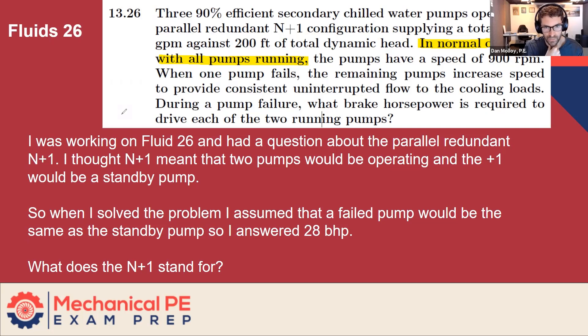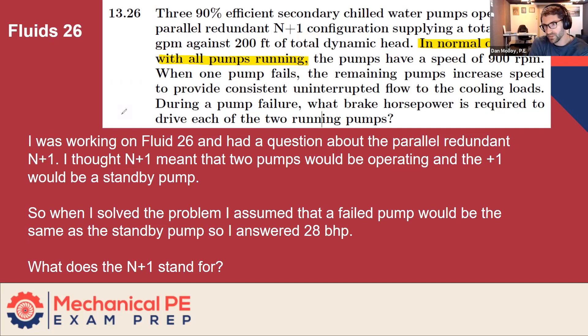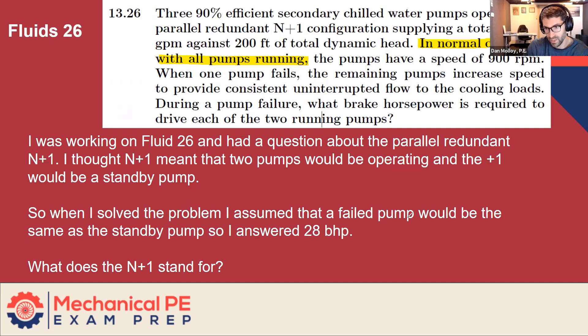We have parallel redundant N plus one. I thought N plus one meant that two pumps would be operating and the plus one would be a standby pump. That's not what was intended here. What was intended was all pumps running in normal operations — running at partial speed, at two-thirds speed. When I saw that, I assumed the failed pump would be the same as a standby pump. If that assumption were true, I would agree. But it's not standby — it was all pumps running.